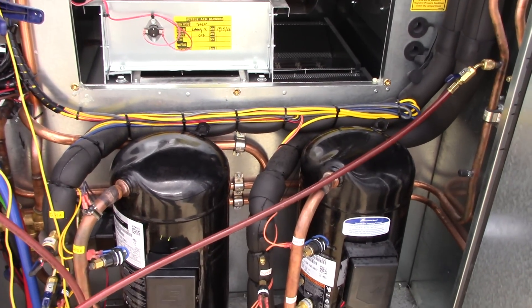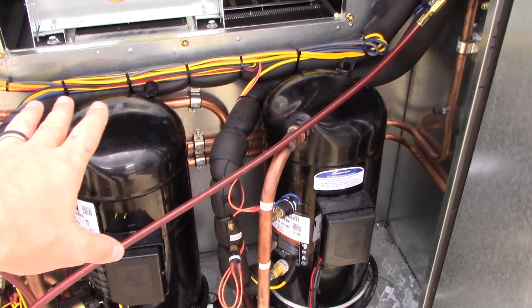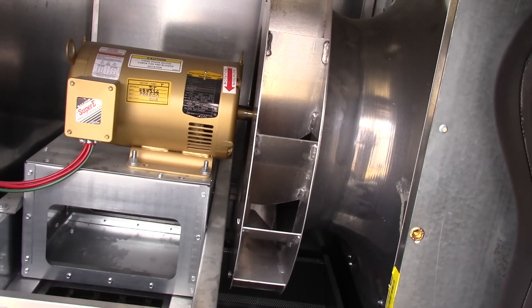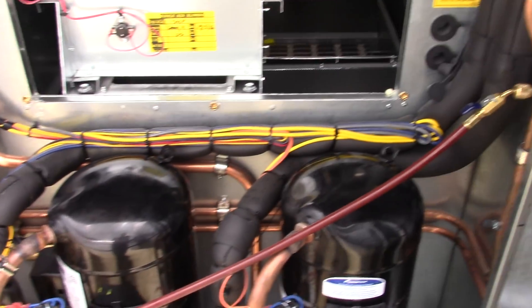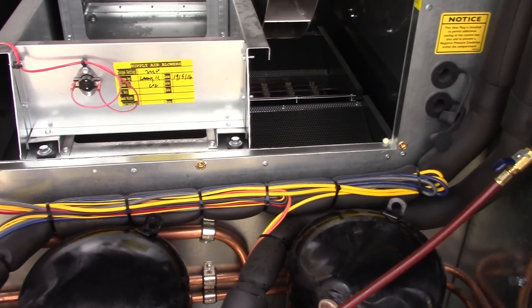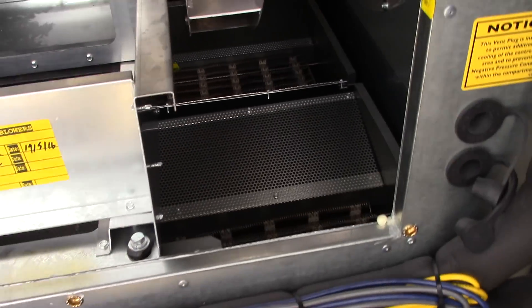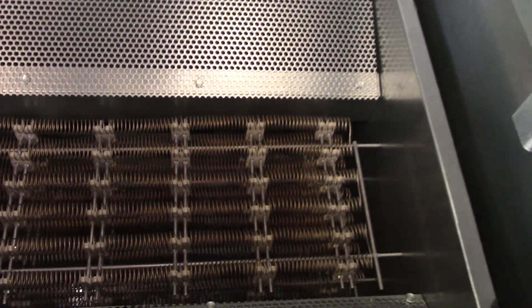Hello YouTube, this is Phillip with Solar Power Electricity and Electronics. I'm going to show you the internal parts of this AAON unit. You've got the high-pressure static fan, a three-phase variable speed motor, and two compressors — one modulates for a reheat coil and one runs at full blast. The modulator is right there, and I want to show you how much electric heat is on this.